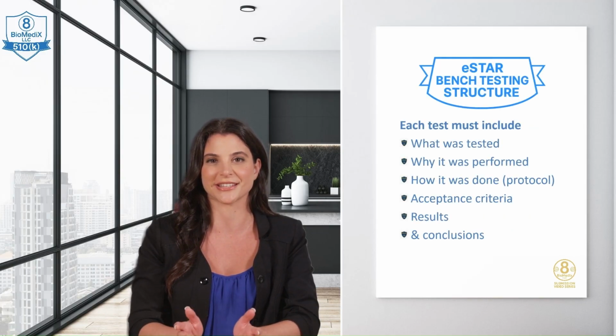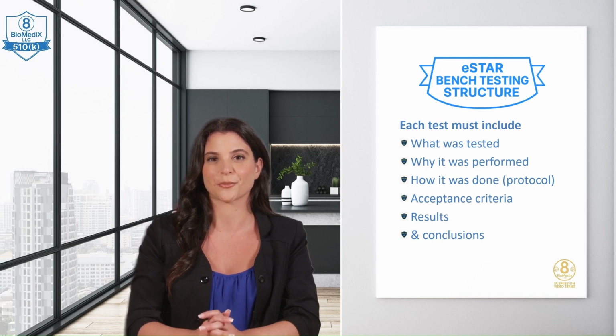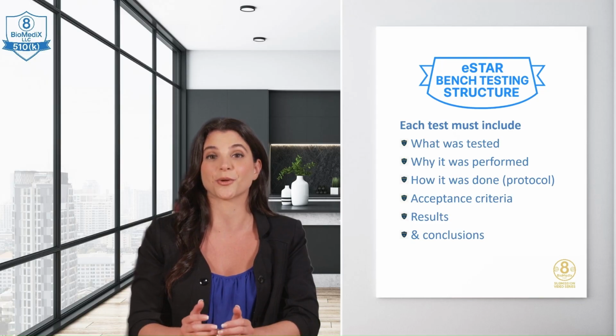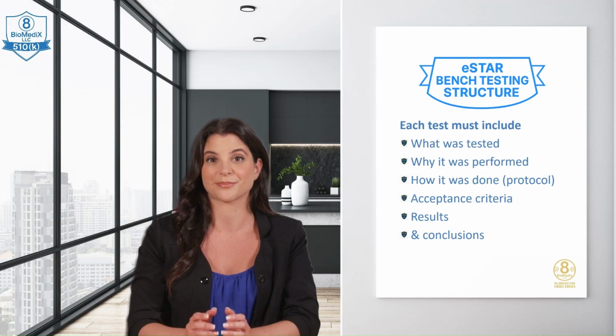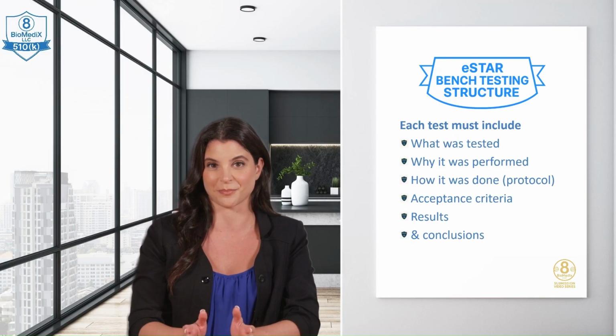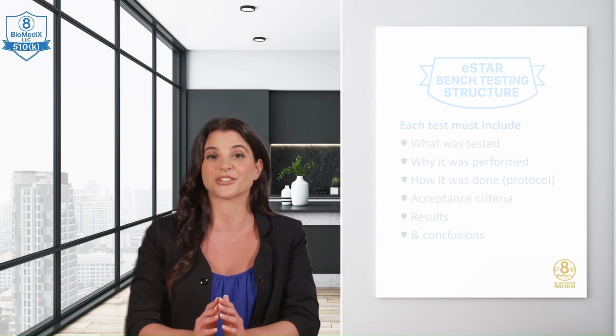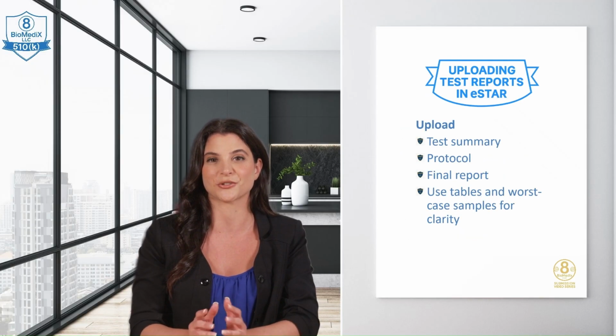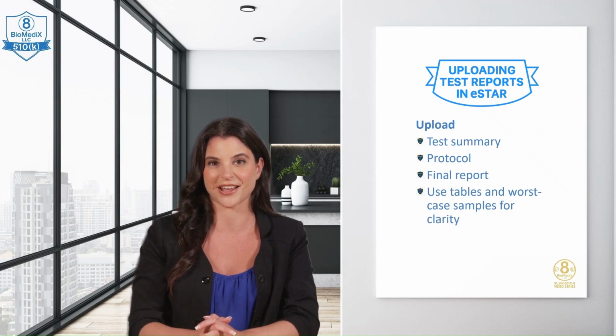For each test, eSTAR guides you through fields that ask: What was tested? Why was the test performed? How was it done? Reference your protocol. What were the acceptance criteria? What were the results? And what's the conclusion? You'll upload your test summary, protocol, and final report as attachments. Use tables whenever possible for clarity. Also justify your testing approach. Use worst-case samples. Define pass-fail criteria in your protocol and explain why the test method was appropriate.